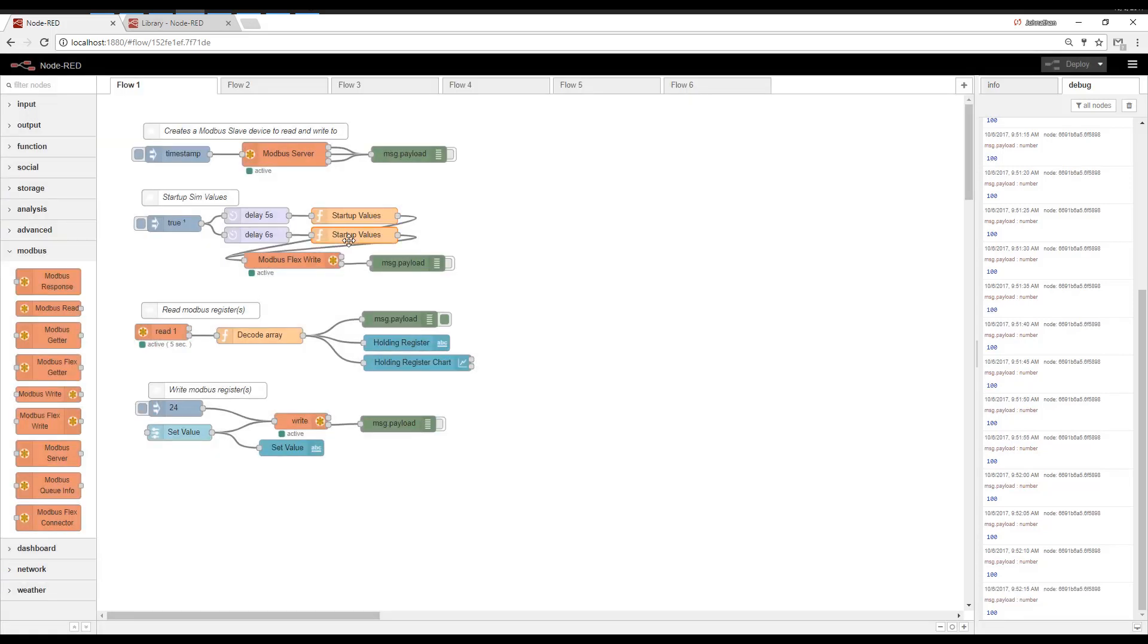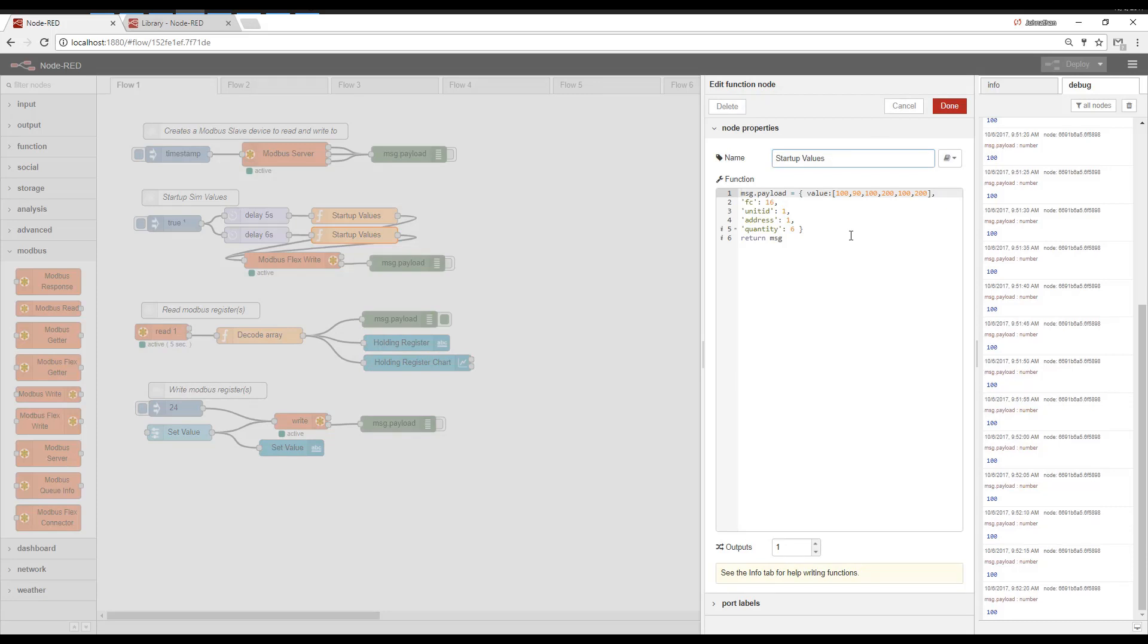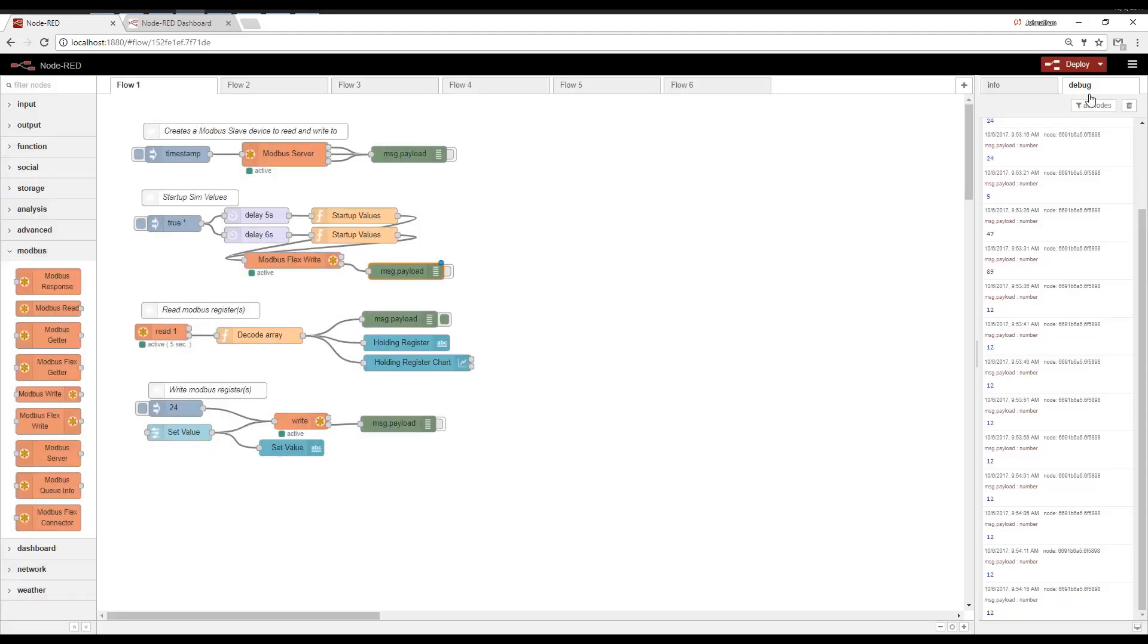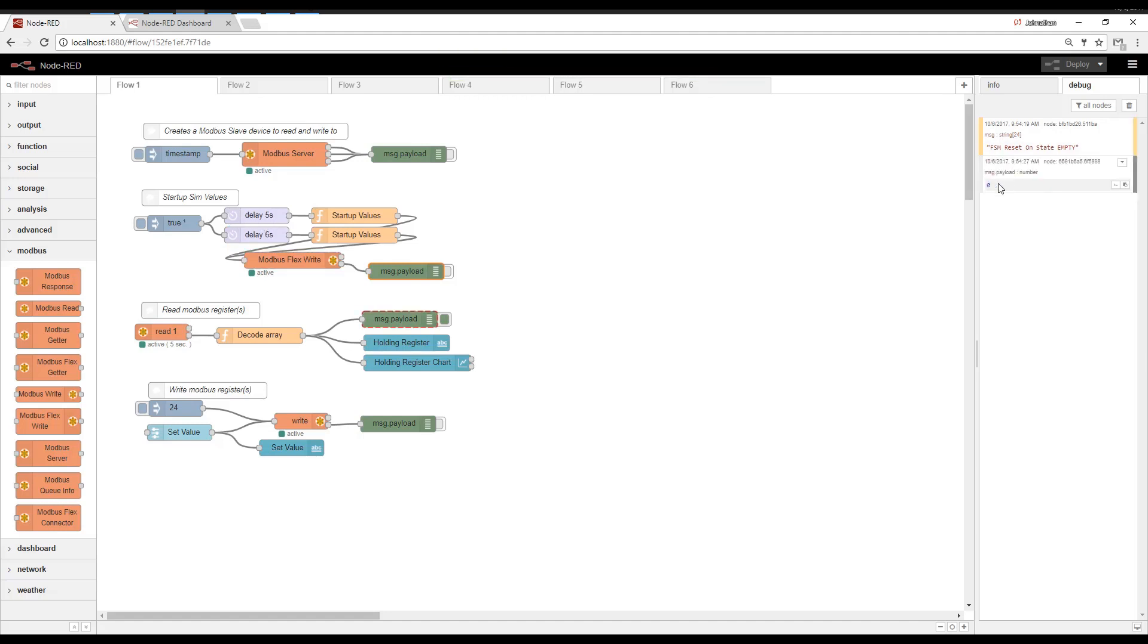We're going to do a similar thing to some analogs here. These are holding registers. And here are the six values we're going to write. So observe, whenever we deploy, let's go ahead and make a slight change. Deploy. This inject sets these timers off. We're going to read the value. It was zero because we restarted. Then the startup values were loaded. And then that register went to 100.